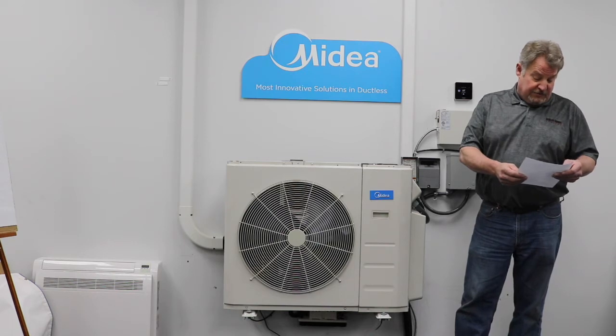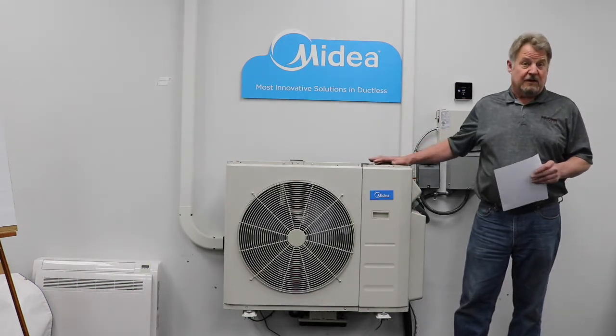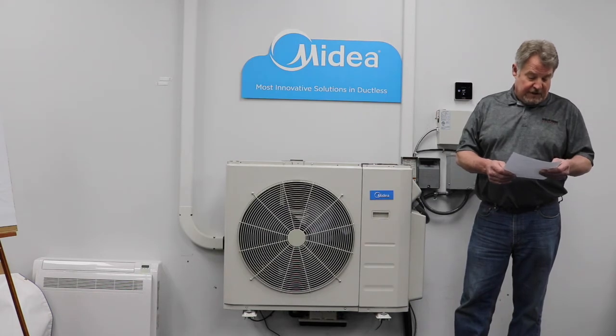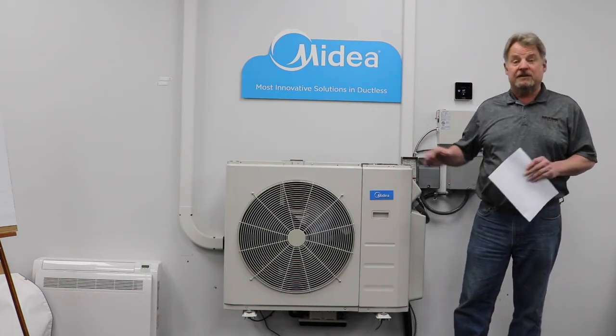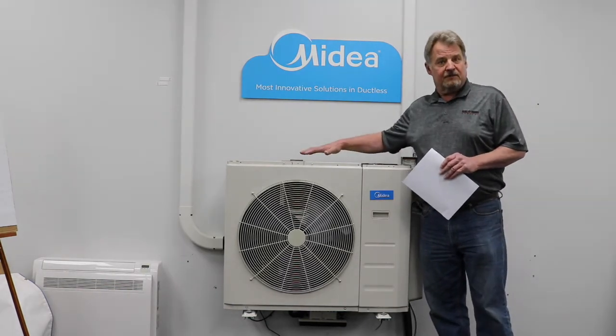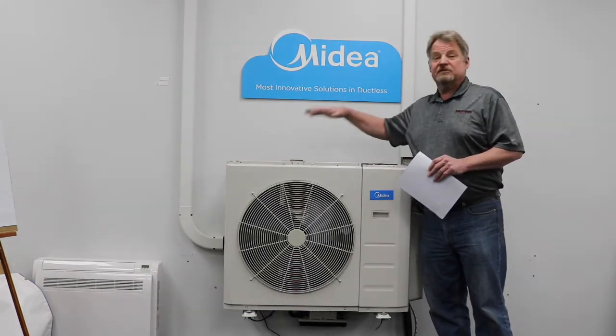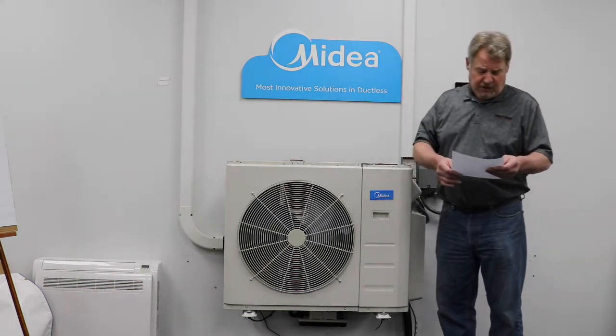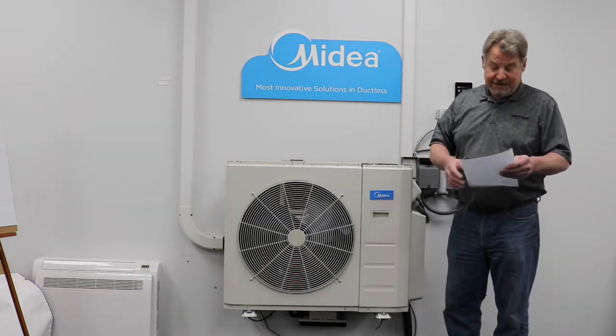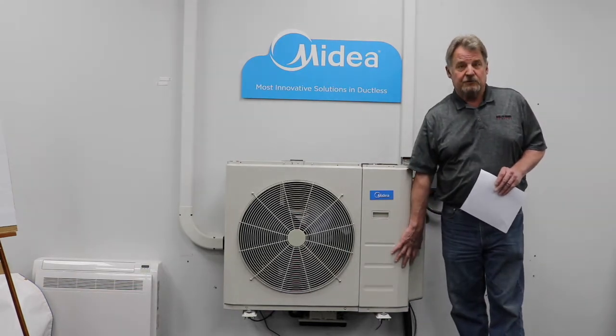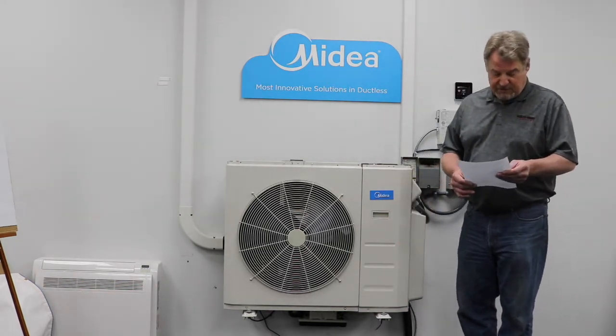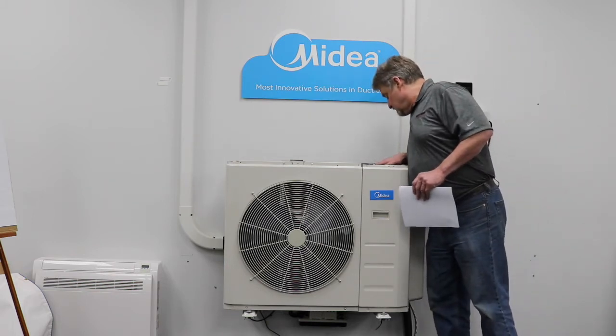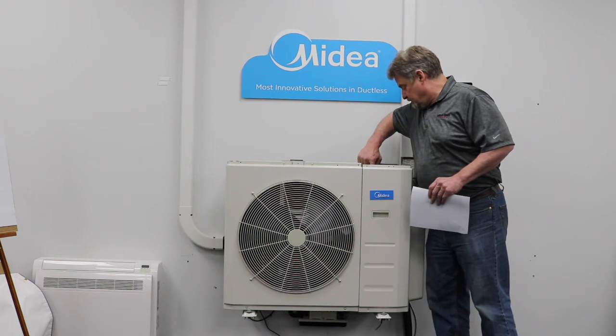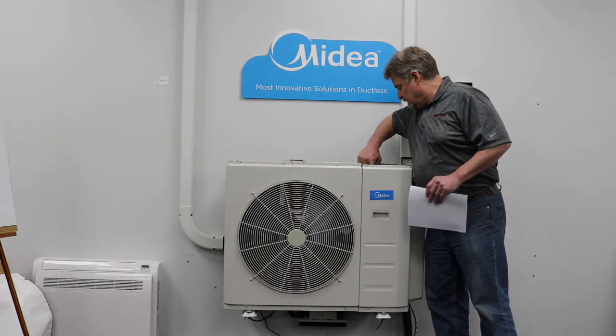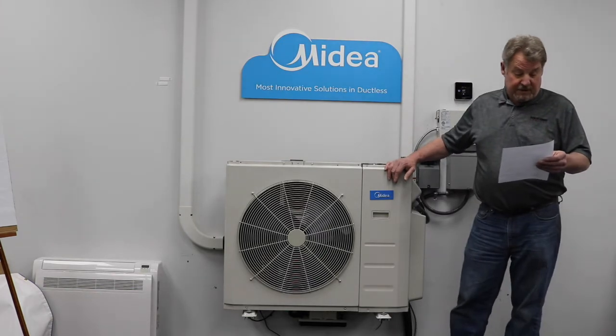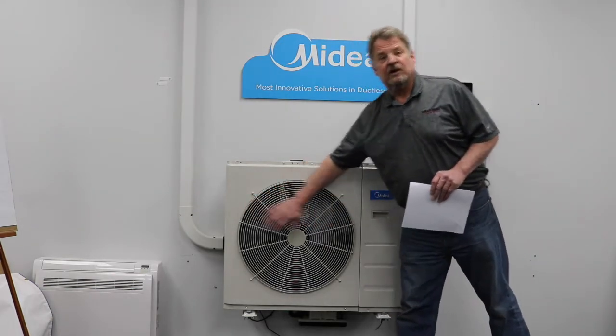The next thing is 8 through 12 tells me the demand of each fan coil. If I go a little further on the line, it tells me what my demand code is, so what demand the unit's calling for, what the frequency is, and also what frequency is being sent to the compressor. A little further on the line, from 17 to 21, tells me what the suction sensors are reading on each one of the ports. So if I were to press this one 17 times, it will tell me what the port A sensor is reading on the suction line.